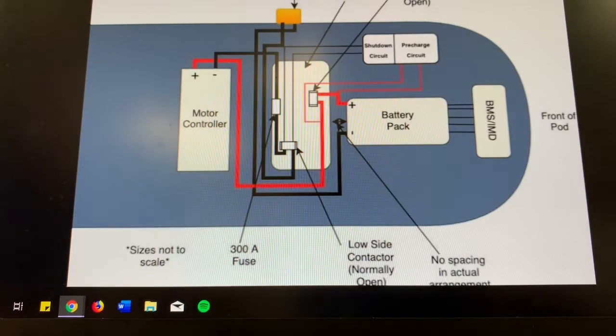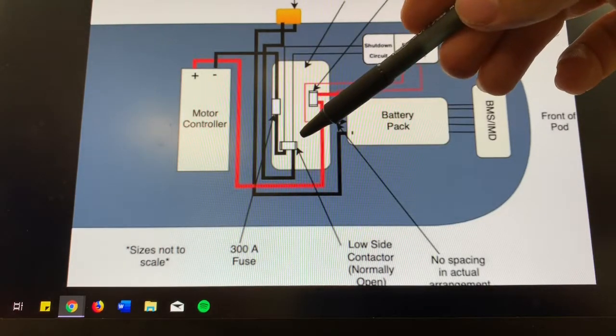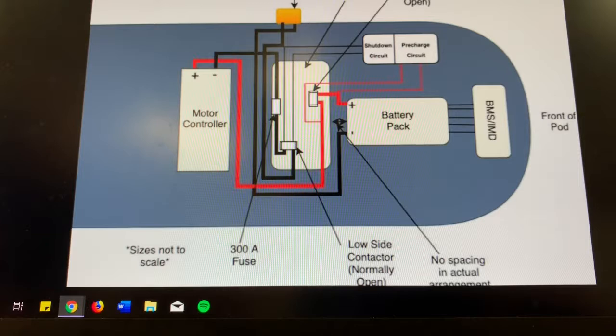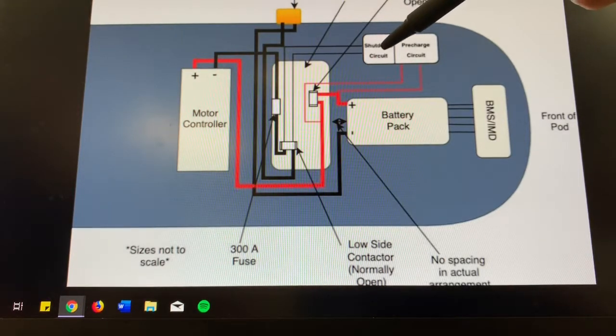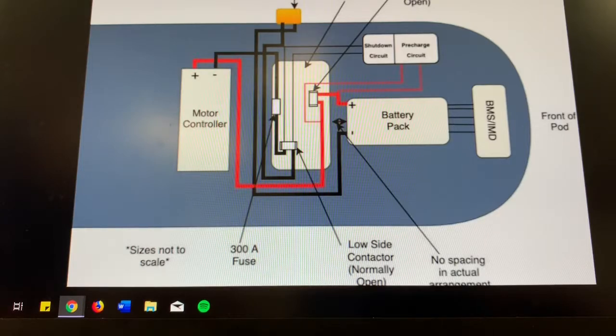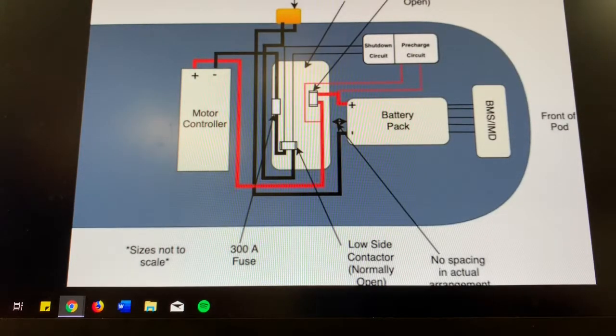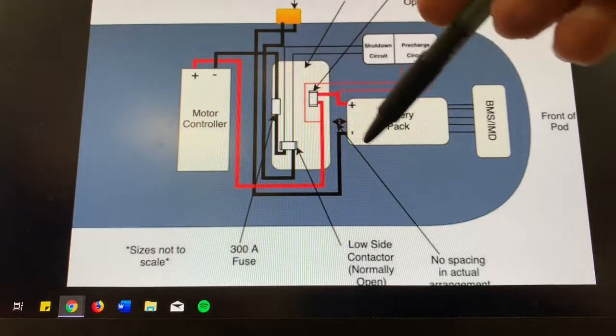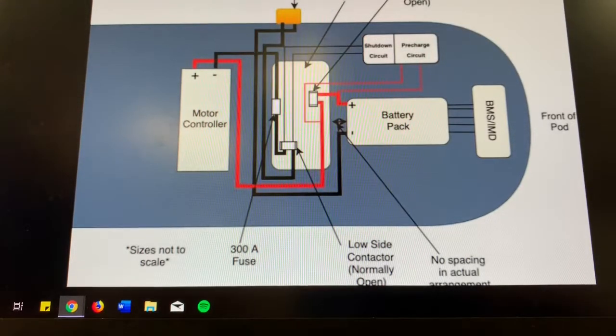Basically, all these different inputs need to be in a go or okay state for this low voltage, or low side, contactor to be engaged. If any of those inputs to the shutdown circuit are in a fault state, this low side contactor will not be able to engage, and the battery pack will not have a complete circuit to the motor controller, so it won't be energized effectively.